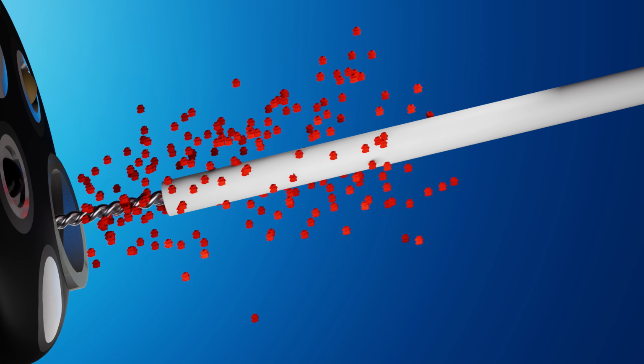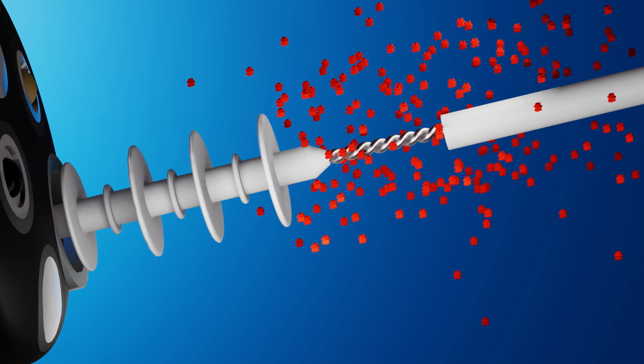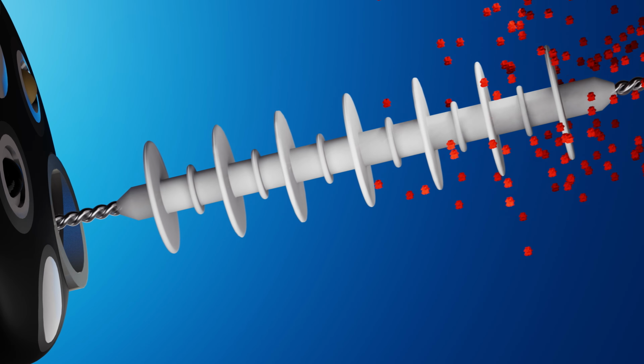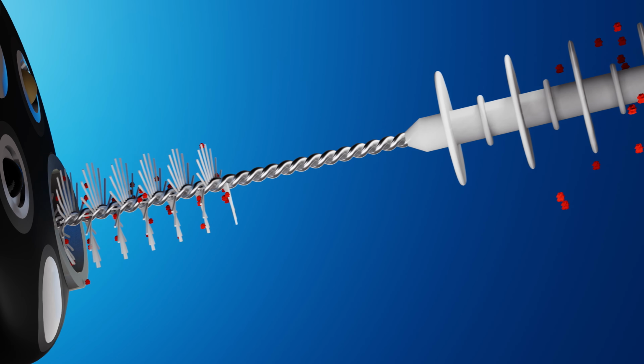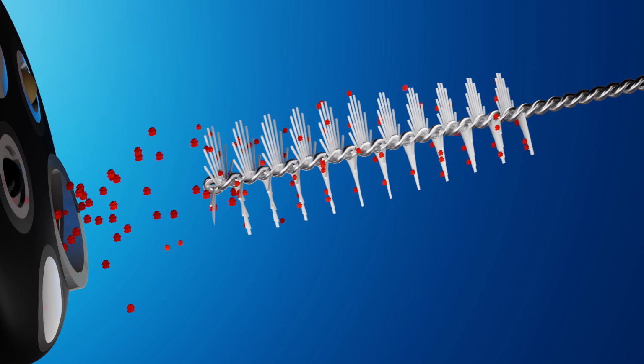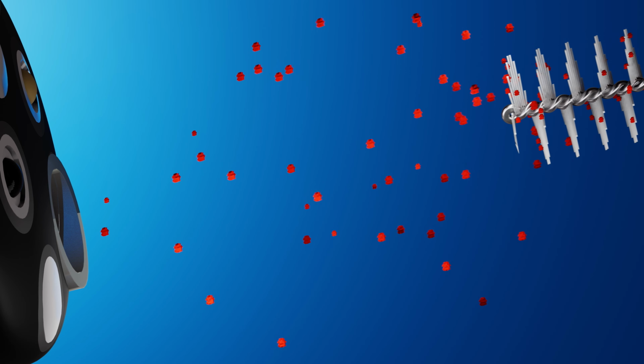Other currently available squeegee-type brushes are not able to effectively clean worn channels or remove the biofilm. As the Squeegee multi-disc wiper and the tail brush exit the endoscope, expelling all the debris, the final flush with clean water leaves the channel nearly entirely free from bioburden. In summary, the innovative three-stage construction of the SuperDART ensures consistent, validated outcomes for the manual cleaning of the channels in just one pass through the endoscope. It saves time and reduces operators' fatigue.